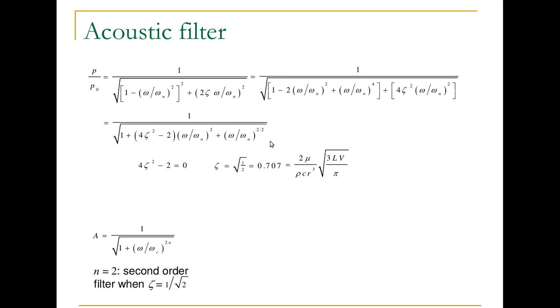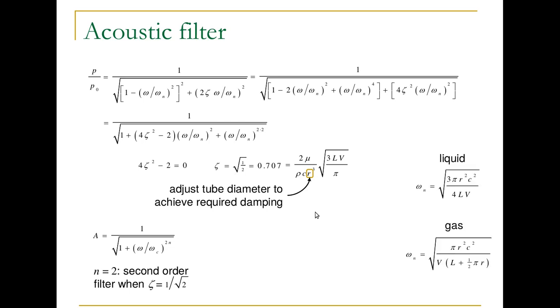It's possible to tune the system in order to get the cutoff frequency and damping ratio that you desire. If you have different values of tube radius, then you can adjust the damping ratio and you can change the natural frequency or cutoff frequency by adjusting the length. So using those two parameters, you can tune your low-pass filter for the pressure transducer.